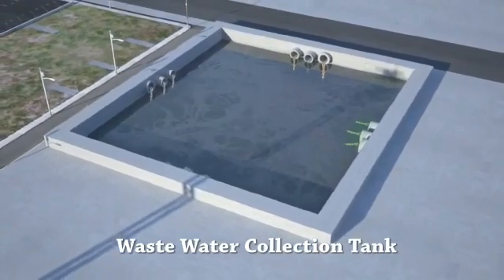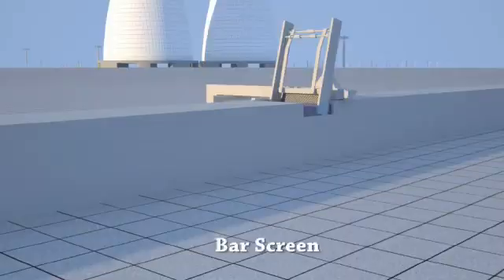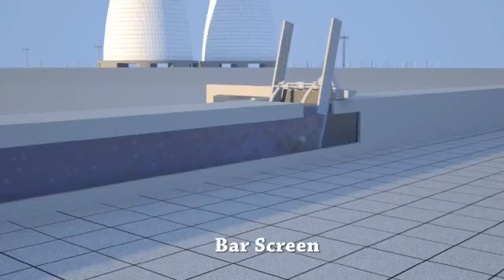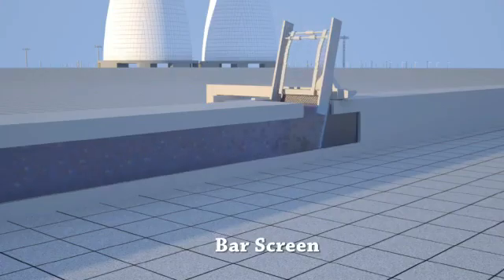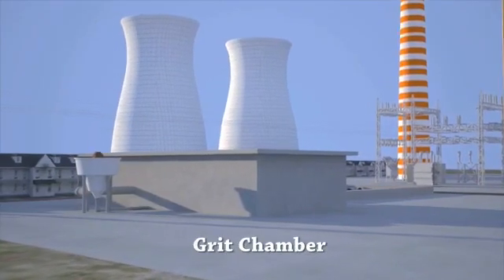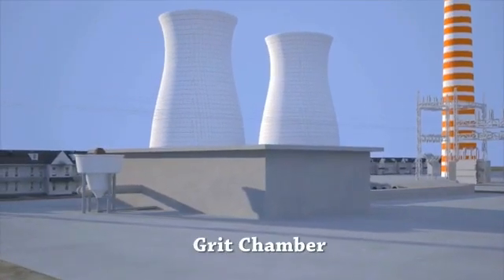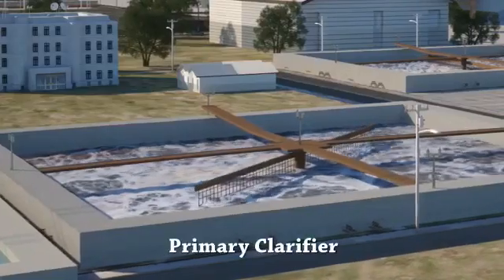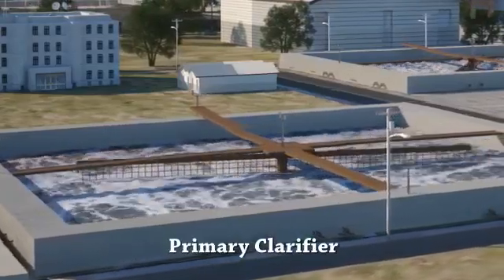ETP has several treatment stages. Wastewater treatment. In the primary stage, wastewater first passes through bar screens to remove large solid objects and then through a grit chamber to eliminate grit like ash, clinkers, etc. Finally, it enters the primary clarifier to remove sediments.